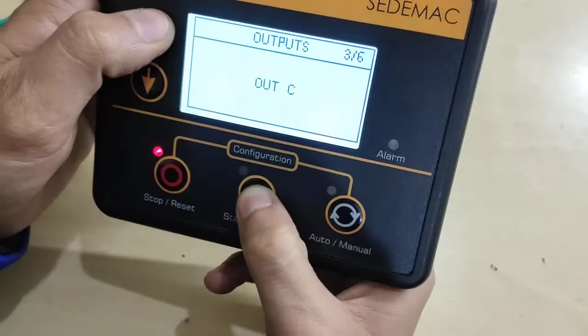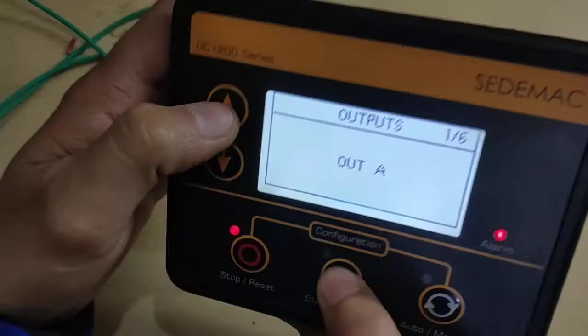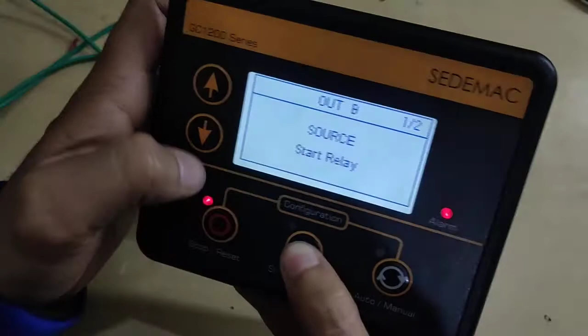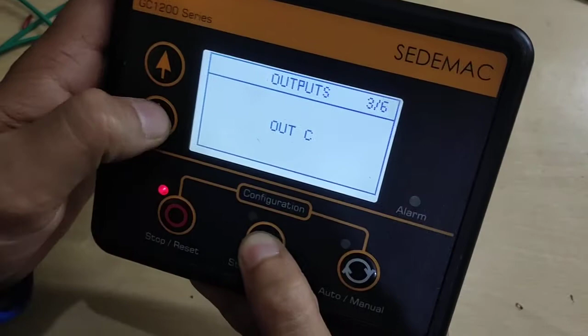This is input. Then there is output A, what to configure at output A, output B, output C, output D. You can adjust it here. It is disabled in this one. For B, it will give a command to the start relay. The 12-volt positive output will come from here. C is for the stop solenoid, and D is for close genset, close mains controller contactor. Here are the output functions, and then timers, generator.